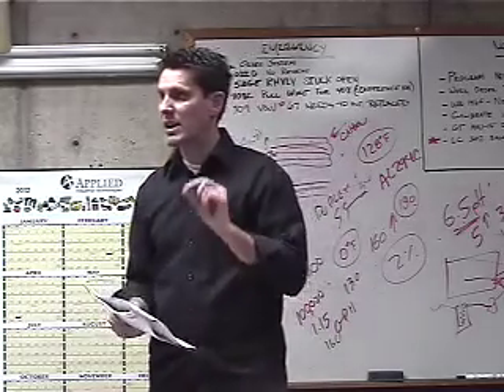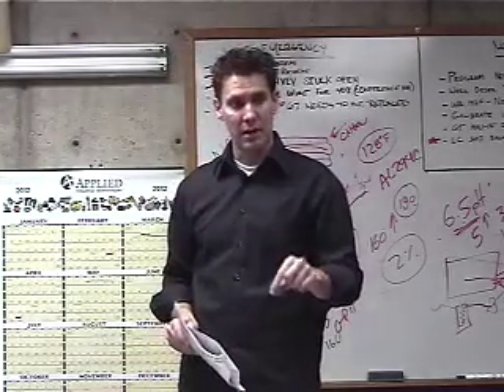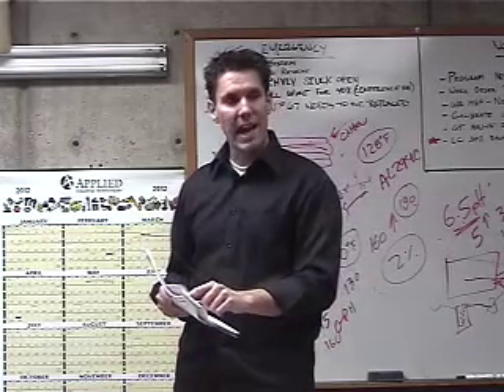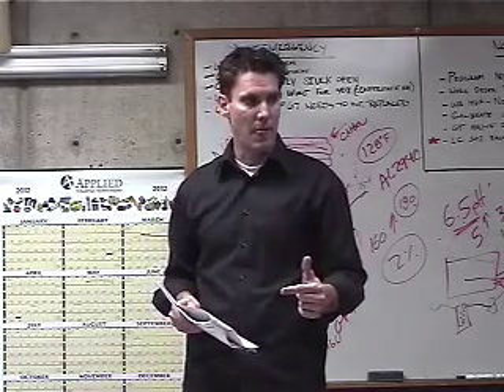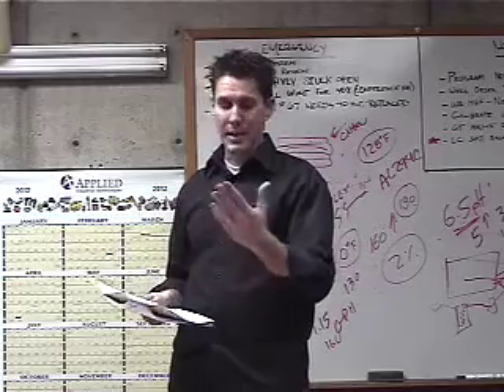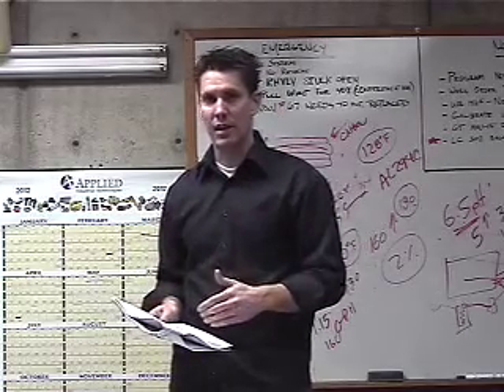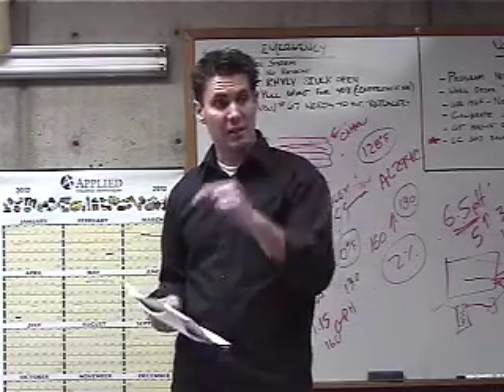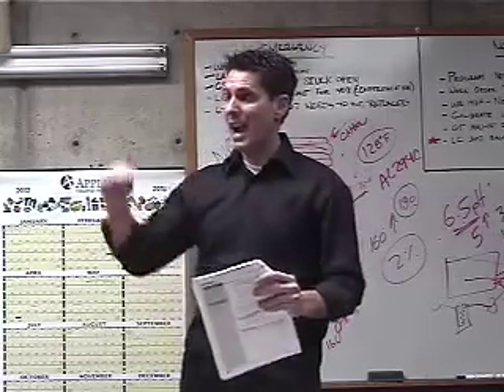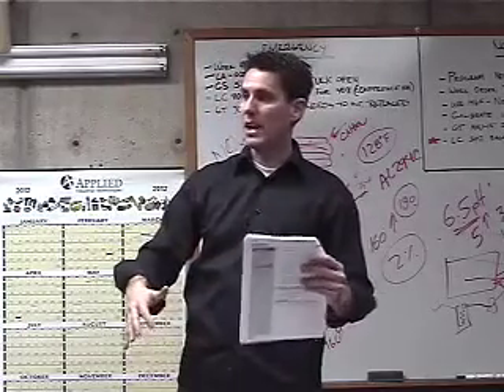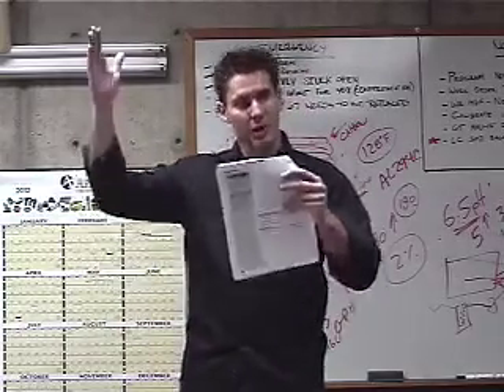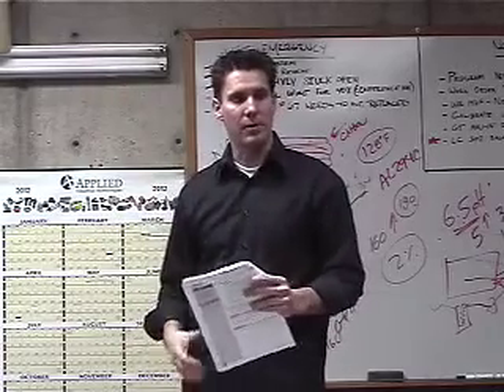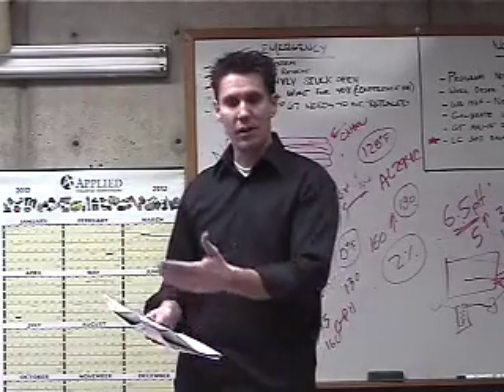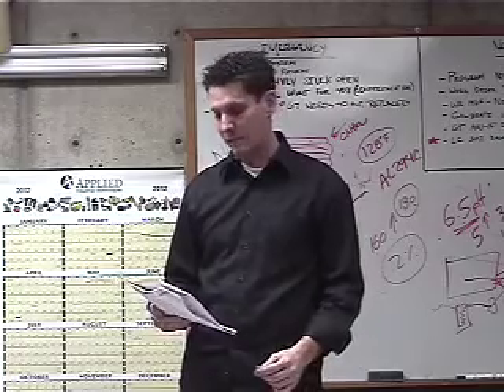Another big one that we see, because of the CSD-1 gas codes here in Utah, we require a low gas pressure switch and a high gas pressure switch. Typically we see that the low gas pressure switch is out. If it's a low gas pressure switch, what's probably happened is you had a spike in your gas pressure because everything came on at the same time, your gas pressure dropped, and it tripped your low gas pressure switch. So if your fan's not starting, again, that's something you might want to check out too.